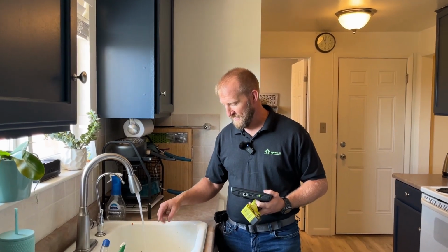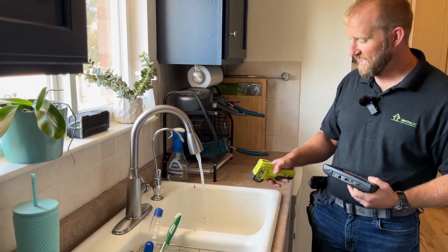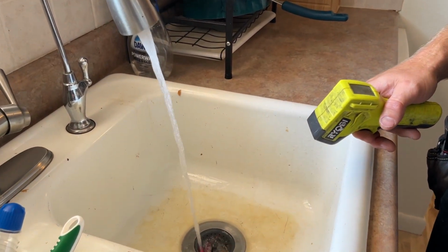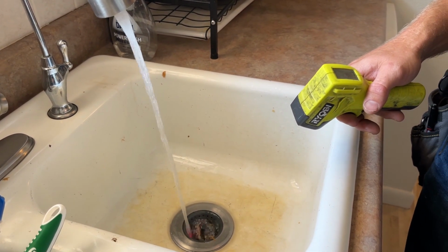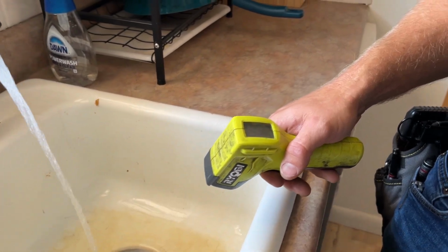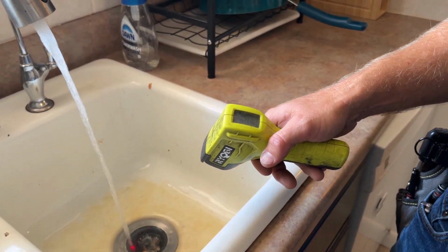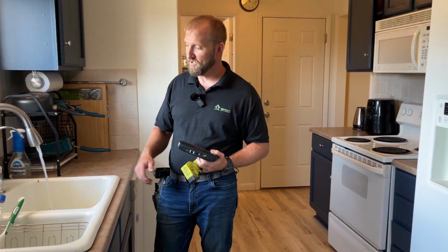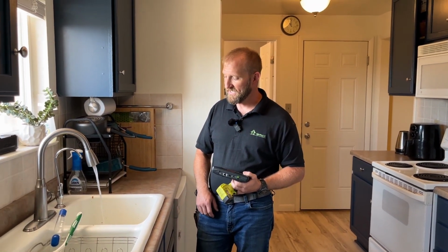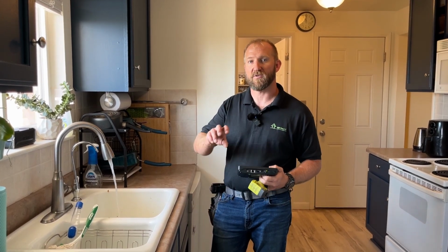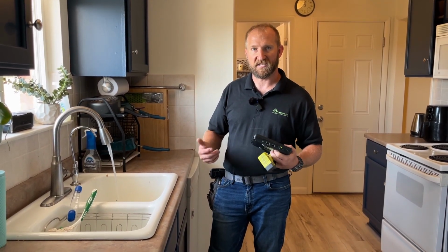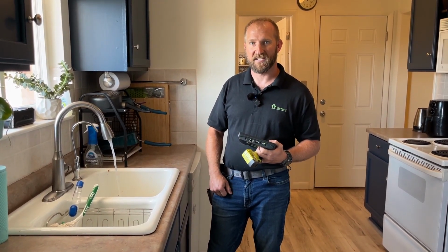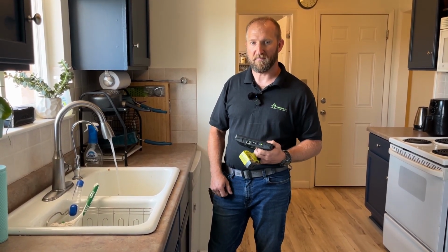Oh yeah, this is getting hot now. Okay, so we can take a reading of the water temperature. 120 degrees is what is recommended coming out at the fixtures, and we're about 130 degrees right now, so we can recommend having them turn down that water temperature just a little bit. We're going to let that run for just another minute or two, get a little bit more water out of the tank so that when we are ready to kick the tank on to check the CO levels in the flue, we'll have plenty of time to do so.